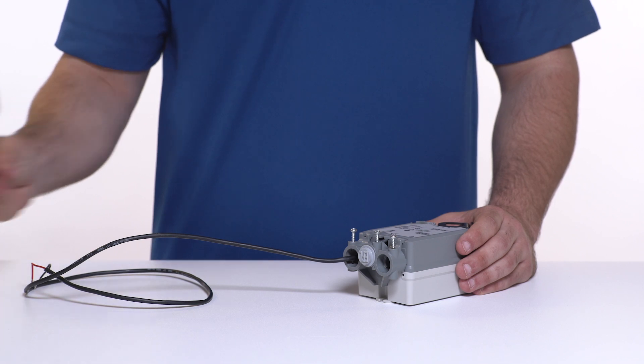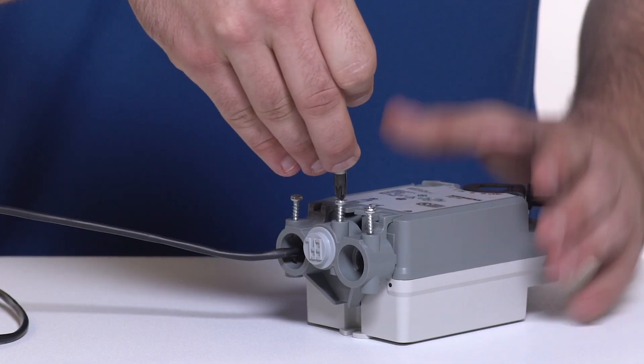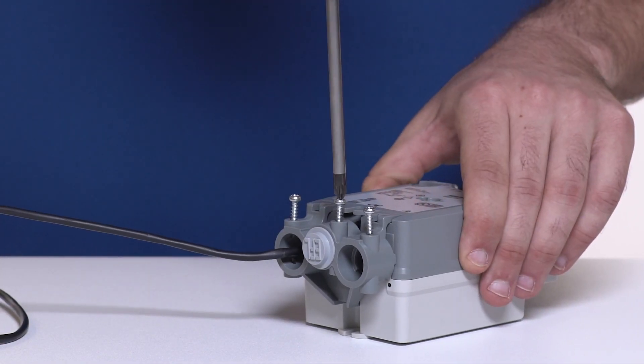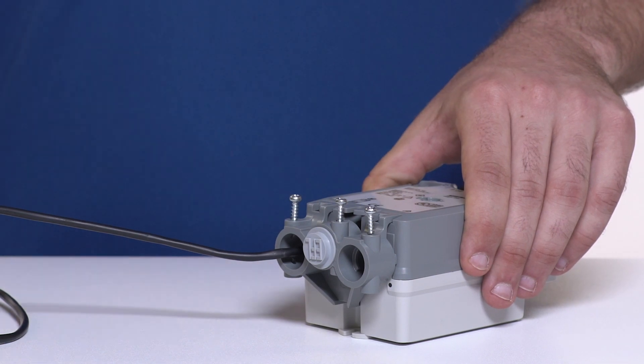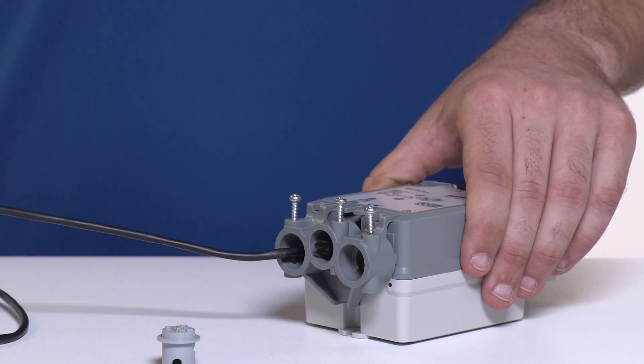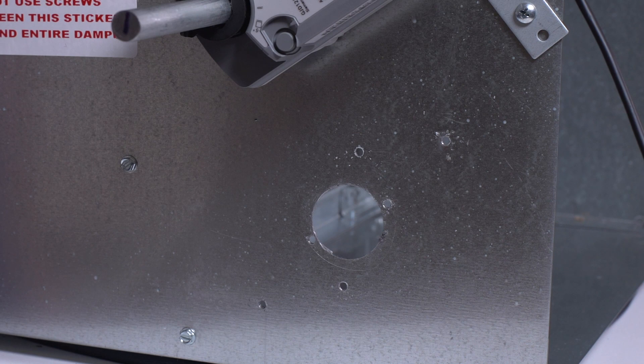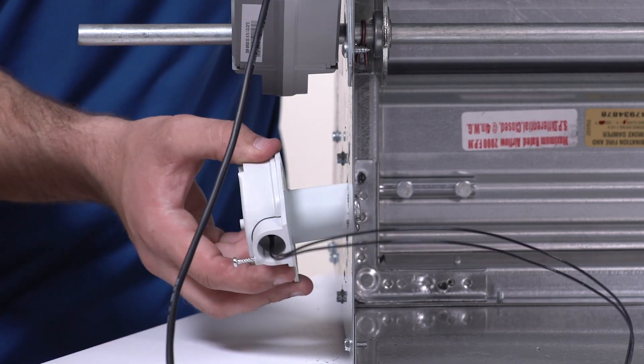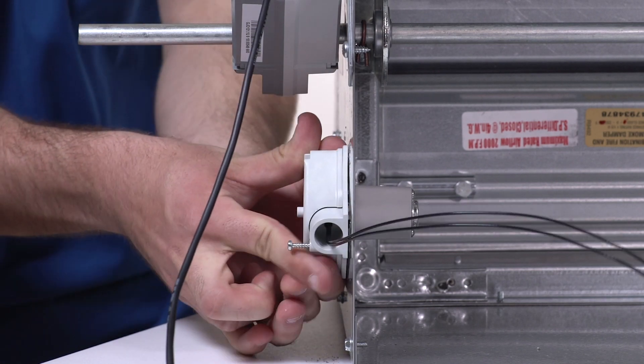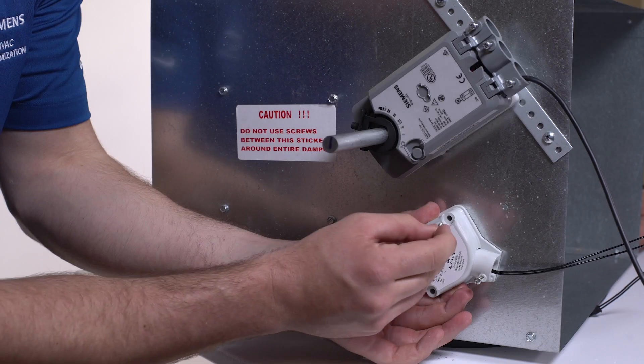If the electronic fusible link will be used, prepare the center conduit adapter on the actuator. Loosen the center screw to remove the EFL plug. Make a 1 3/8 inch diameter hole in the duct wall or damper's sleeve. The sensor will protrude into the duct or damper for proper temperature sensing.